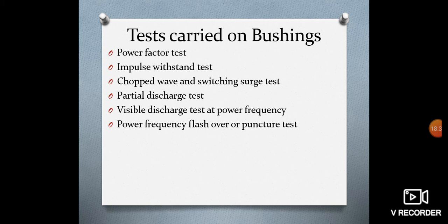Next we have the chopped wave and switching surge test. Chopped wave and switching surge tests of appropriate duration are carried out on high voltage bushings. The procedure is identical to that of the impulse withstand test. Partial discharge test. In order to determine whether there is deterioration of the insulation used in the bushing, this test is carried out.